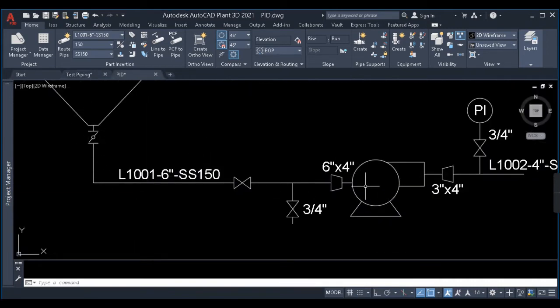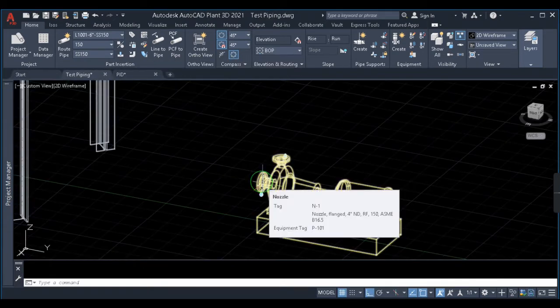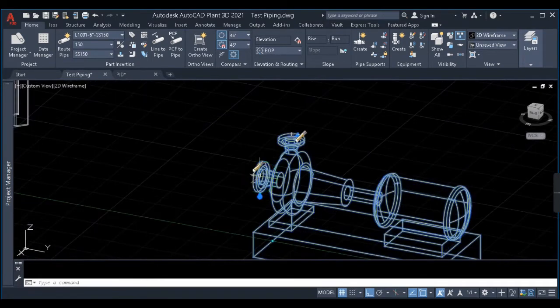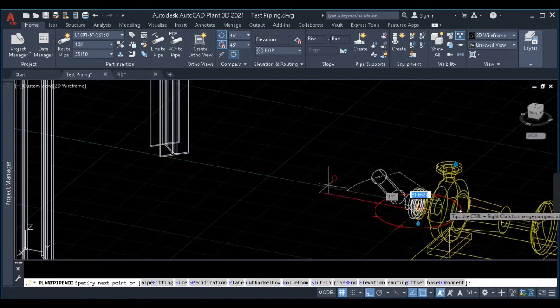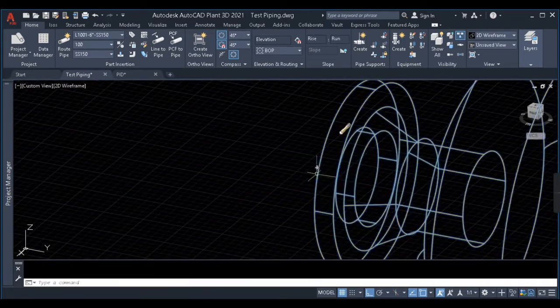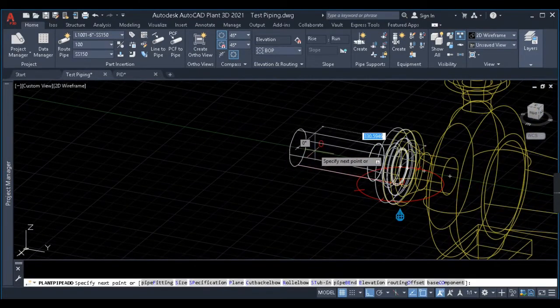Now let's start routing. First let's model the inlet line to the pump, starting from the inlet nozzle. The size of the nozzle is 4 inch, then comes an eccentric reducer — for every pump inlet we give an eccentric reducer. The reducer is 4 by 6 inch. I'll click on the pump and click the plus sign. If the spec is properly created, the flange should automatically pop out, and you can see it does.